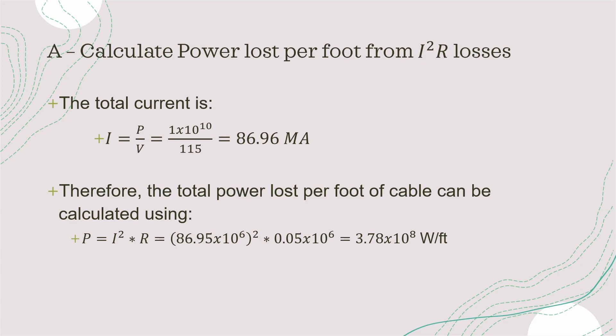P equals I squared times R, so 86.95 times 10 to the 6 squared times 0.05. This gives you a power loss per foot of cable as 3.78 times 10 to the 8, and that's your solution for question A.